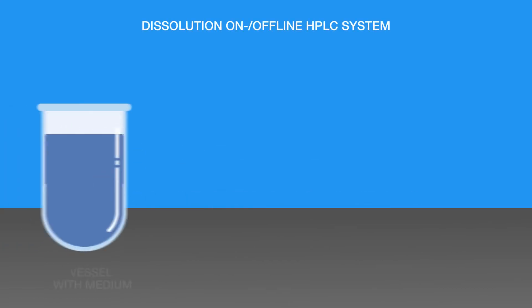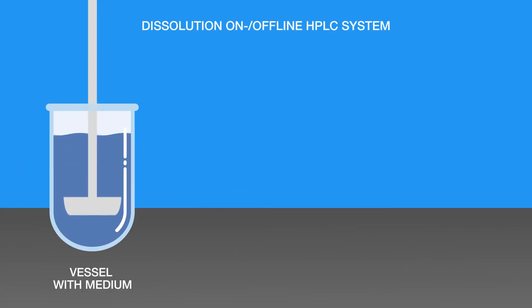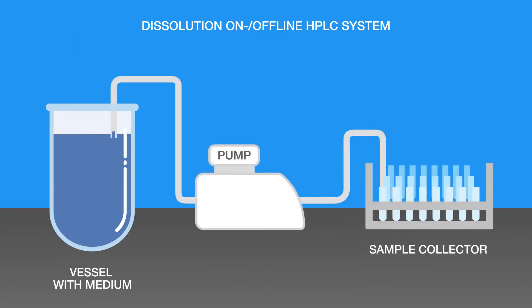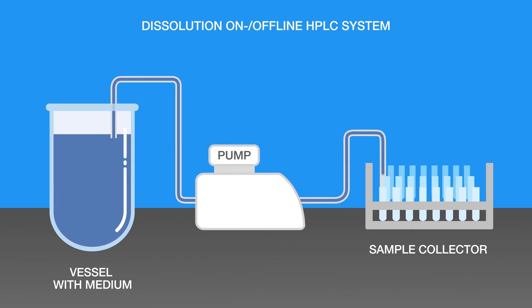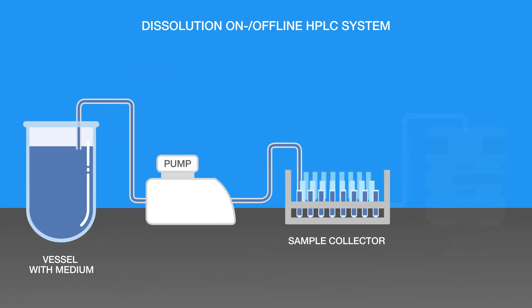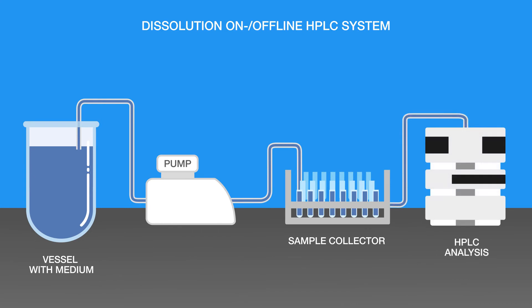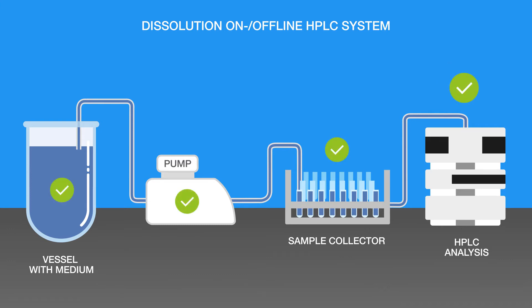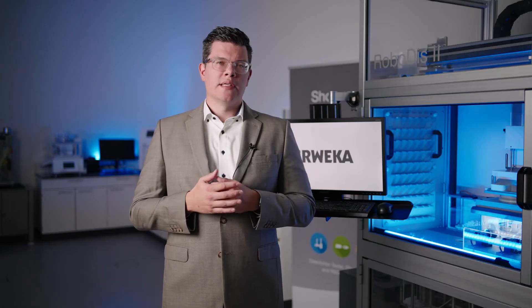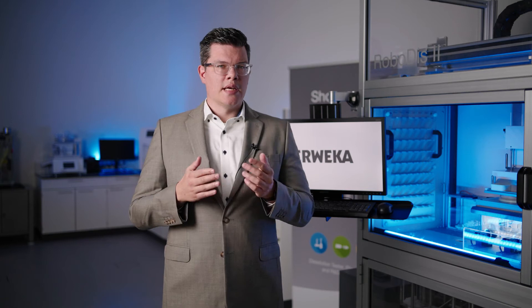With an on-offline HPLC system, the order is reversed — because an HPLC analysis takes more time, the samples are first stored in an autosampler and then afterwards directly injected into the HPLC analysis. ERWEKA's online HPLC approach is unique: it enables full HPLC online analysis automation with no manual steps between the dissolution test and the HPLC analysis.